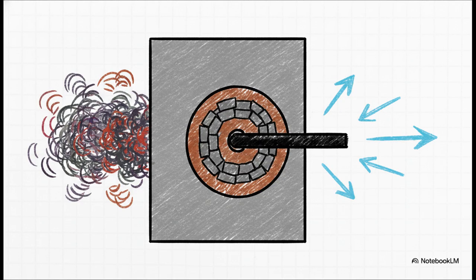So how do we cross these boundaries safely? Well, you can't just drill a hole in a bulkhead and shove a wire through. The codes mandate specific methods. We're talking gas-tight cable transit frames. In some spots, sand seals or mortar sealing are required. If you're using rigid metal conduit, you need conduit sealing fittings packed with a non-shrinking compound.